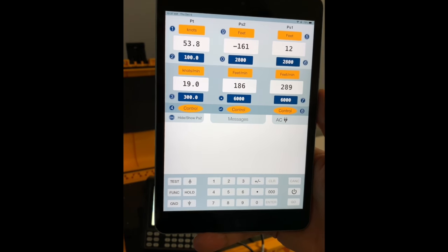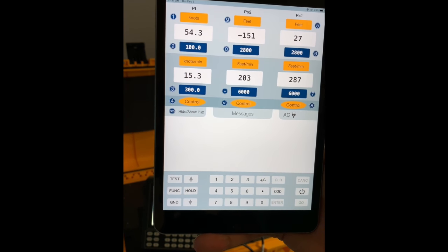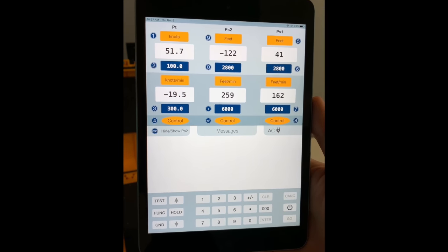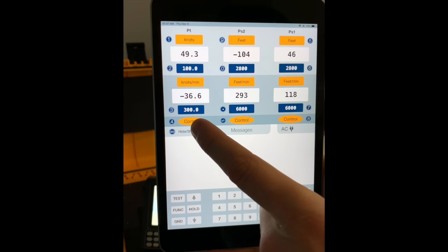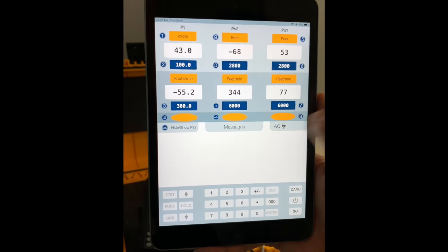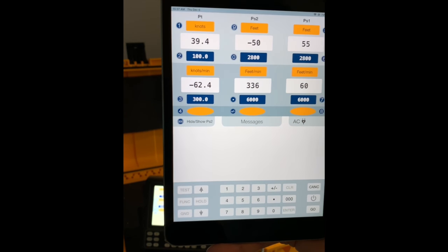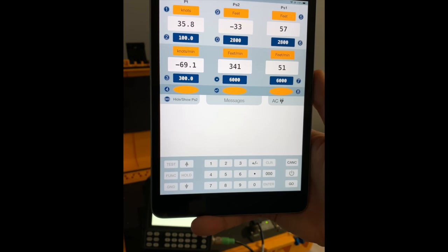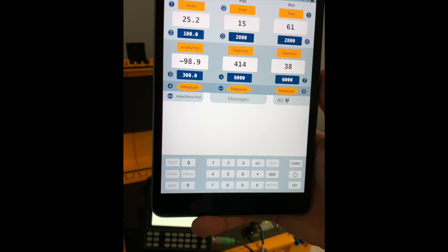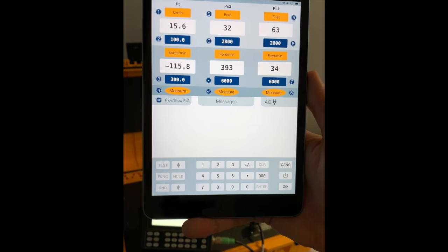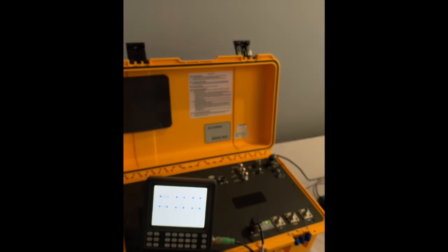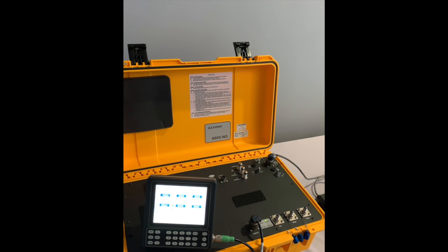There are two things now that you can do. The first is the right thing to do: either change all of your channels here to measure mode or turn off the unit. You have two choices: either turn off the unit and go work on your leak, or switch each channel to measure, as I'm doing now. The advantage of doing this is you wouldn't have to reboot the unit and re-pair the iPad and all of that, so you would save a little bit of time. But when you have a leak that is too large for the tester to handle, switch all three channels to measure or turn off the unit and go work on your leak. There's something obvious going on. When I click on go, the test set will come back to ground that it actually never left because, as you can see, the three channels here were open.